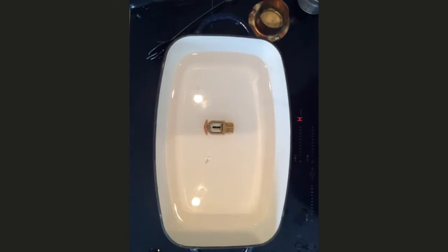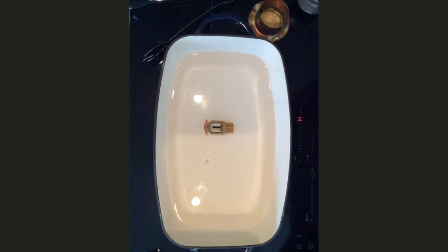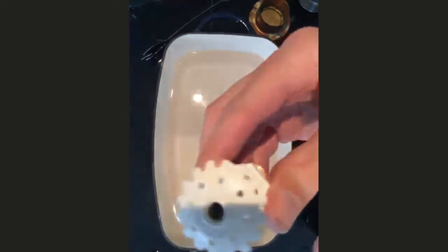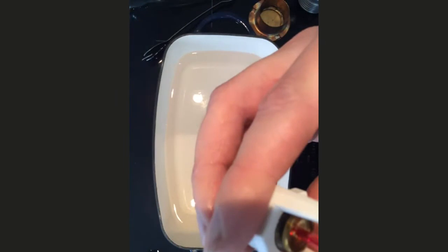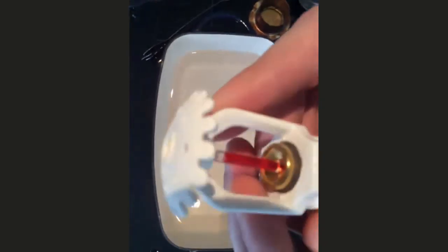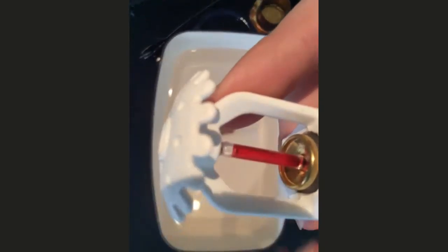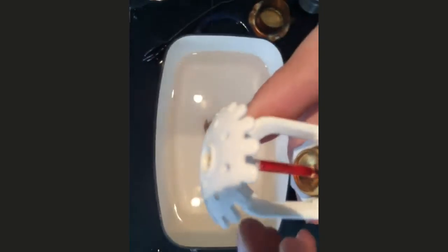See, our green bulb still not operated, which is what I expected to happen. And then ones like this one here, it's marked on the top as CUP. C stands for conventional, as opposed to spray, and that is to do with the way in which the water is discharged, and then the UP means that it can be installed in the upright or in the pendant position.